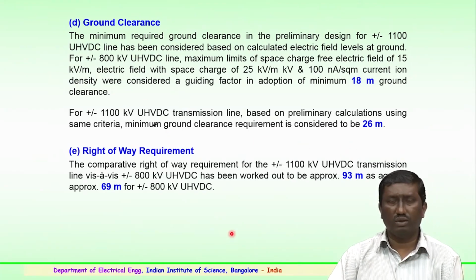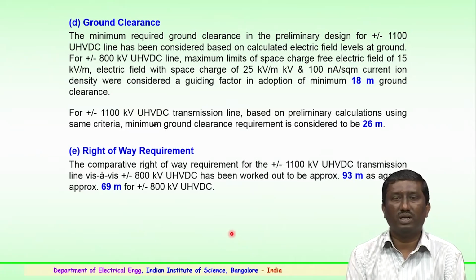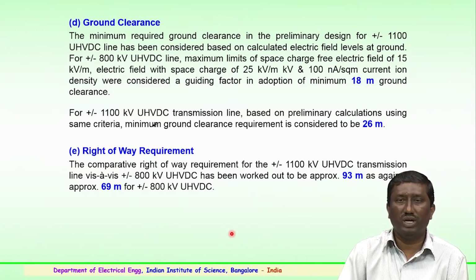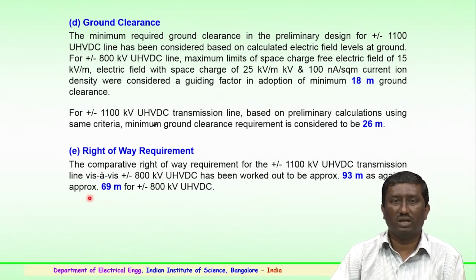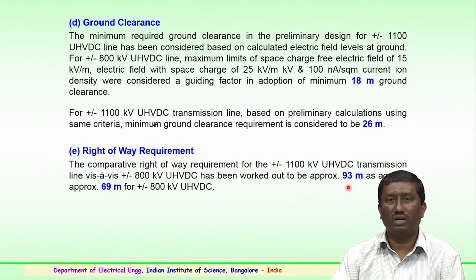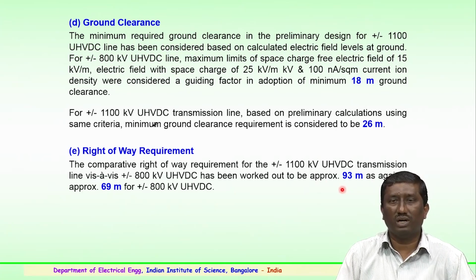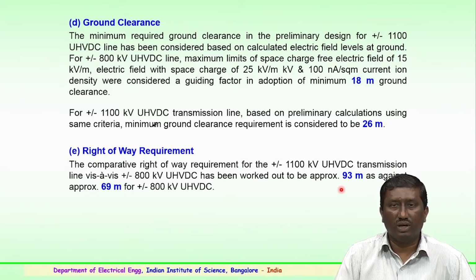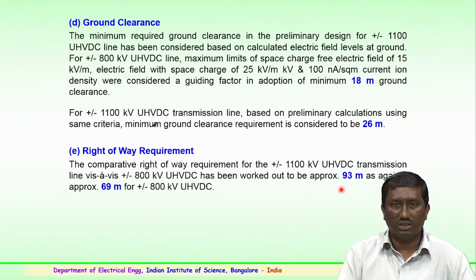Then right of way: the minimum requirement for 800 kV is somewhere around 69 to 70 meters, as you can see here, but when you go for 1100 kV you have to look for a right of way of somewhere around 93 meters. 93 meters is roughly around 280 to 290 feet, roughly 300 feet. So, it is a very large space which is required.